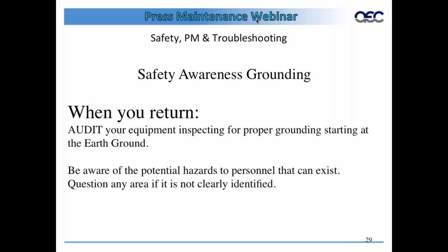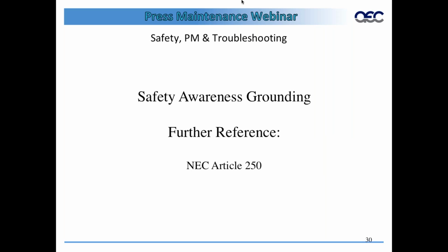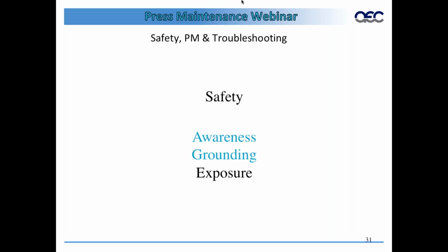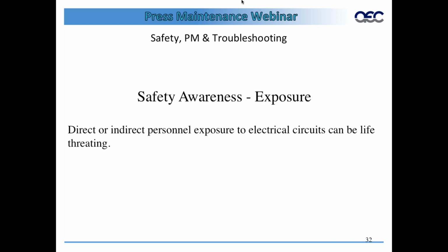or in some way has been altered so that it doesn't have it, and look for the path back to ground. Just because it's grounded at a motor doesn't mean it's grounded at earth ground. For further reference, you can go to your NEC Article 250, where there's a large section on grounding for almost anything that you would do. There are some exceptions, but almost anything that you would do in your facility, there are instructions for grounding.